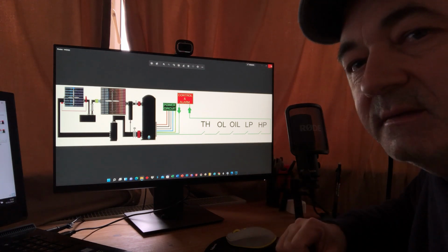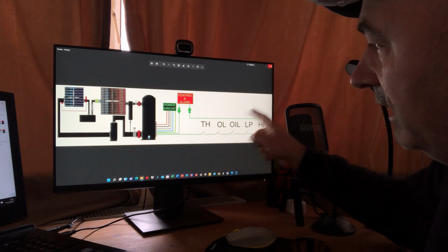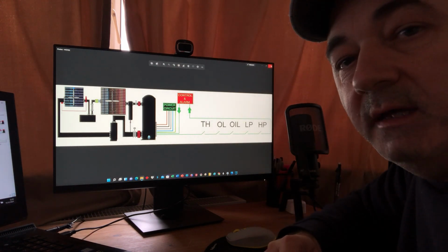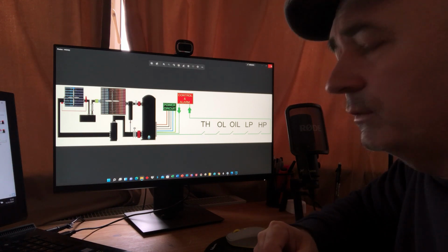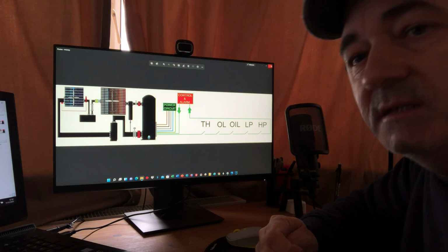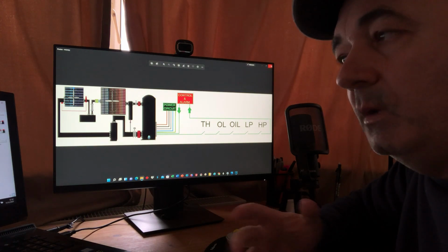This is a bad system from my perspective because all alarms are in series with the thermostat, and this sends the input to control an alarm. So you always have a general alarm. If you have an issue with the system, it won't tell you what's wrong with it.